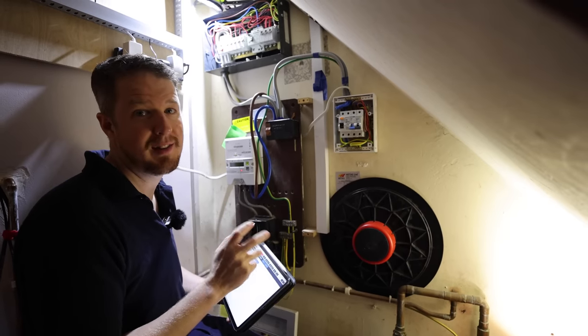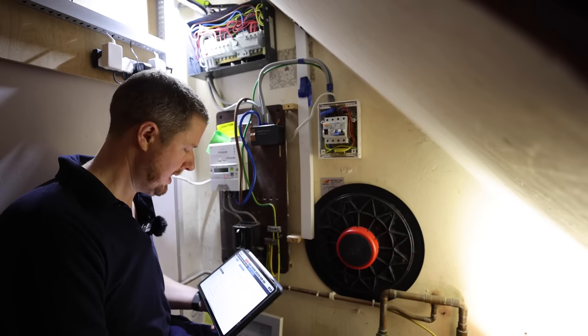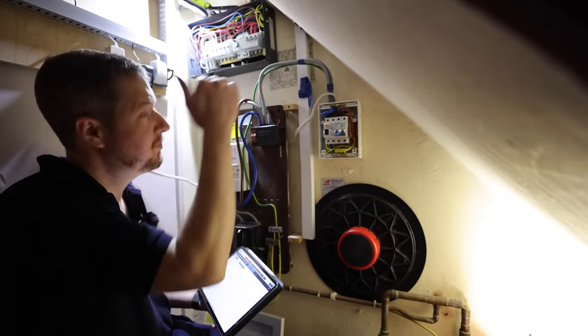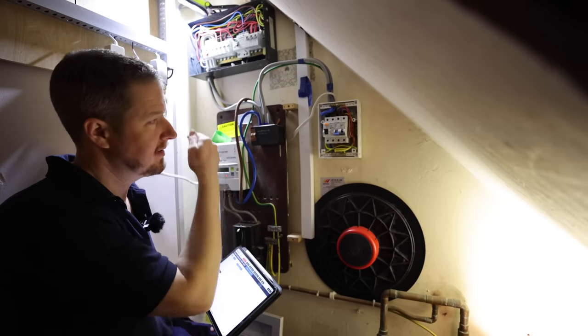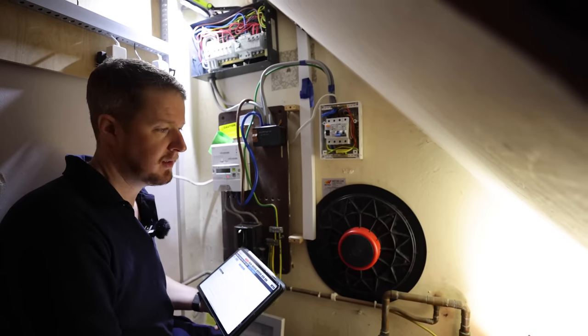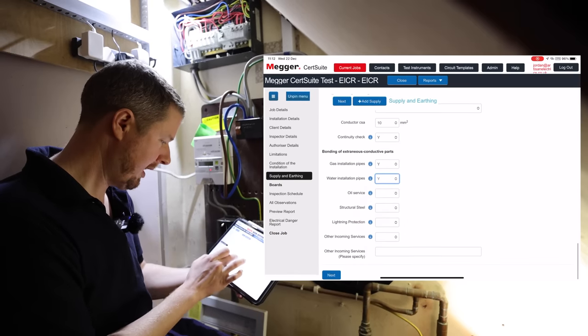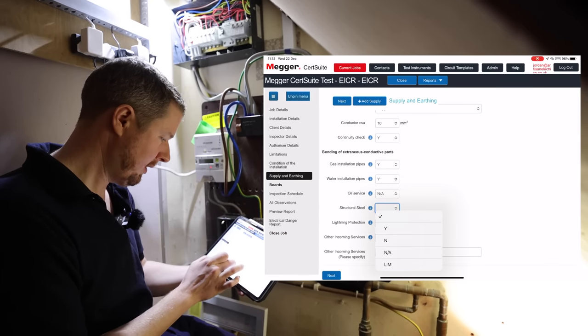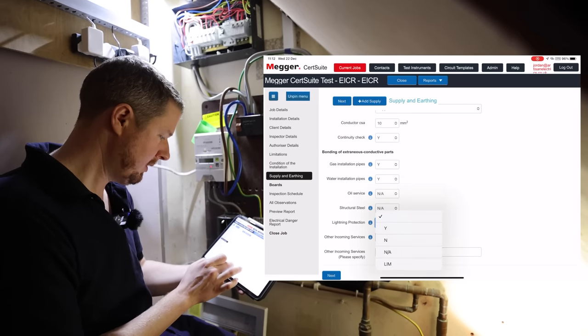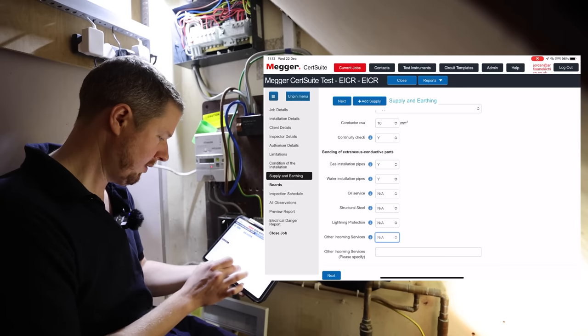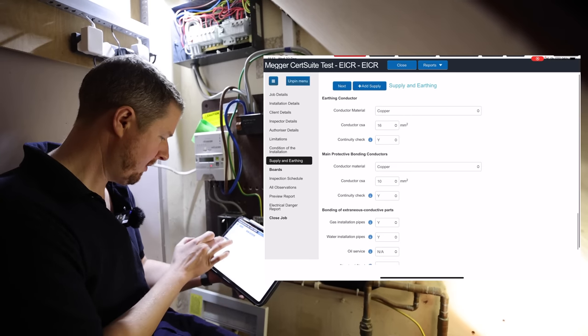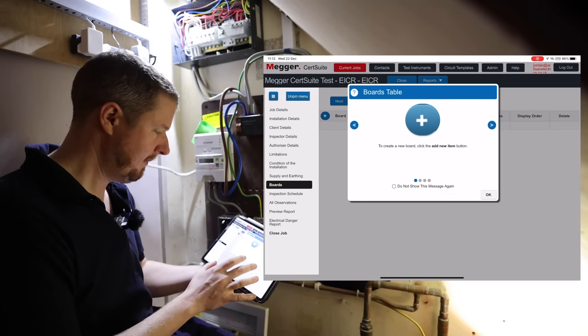There we go, it's on zero now, so that's fine. We're going to clamp on to this with one end, and then we're going to clamp the other end onto our bonding connection, and then we're going to just check that we've got continuity, which we do. We've done our R2 readings, they're all good. What we're going to do now is I'm just going to go through and just add in the circuit schedule for everything, and then we can start doing our R1 and R2 tests.